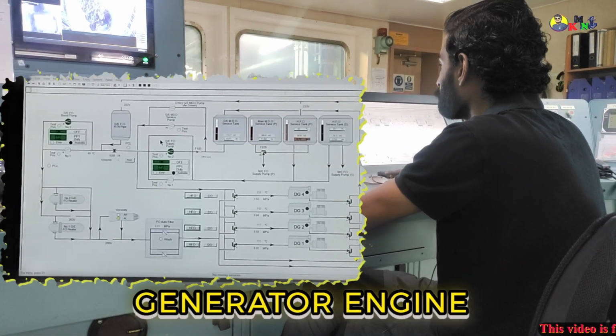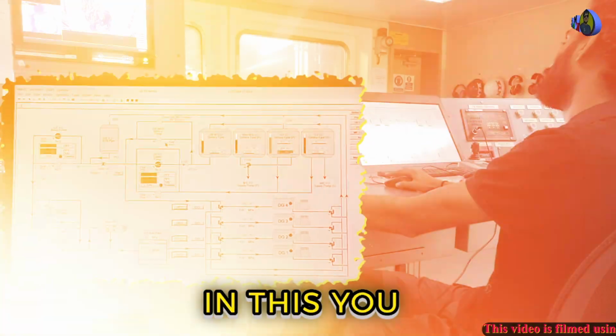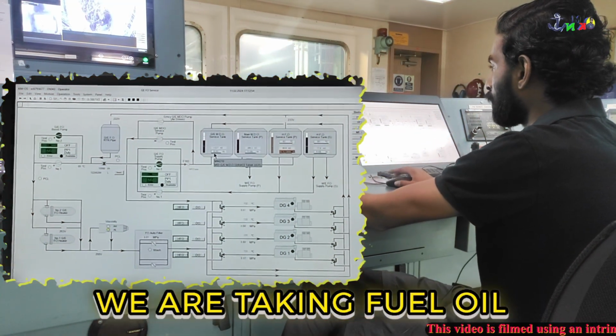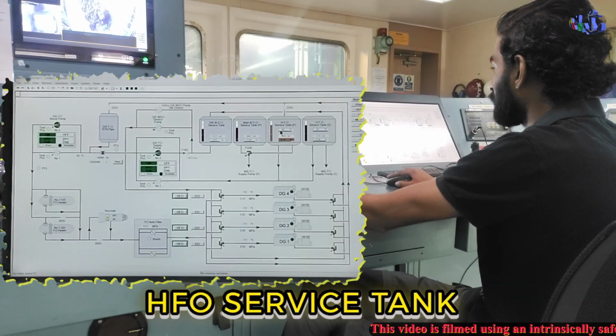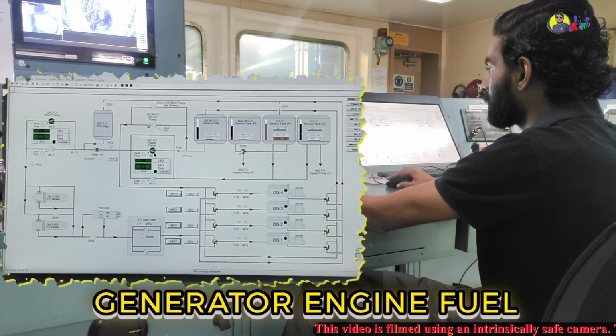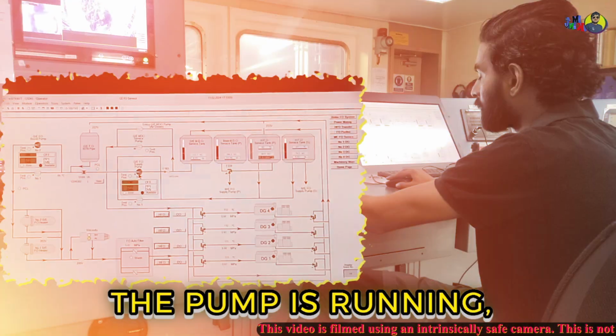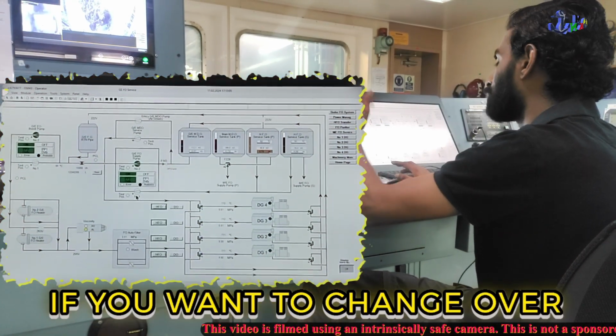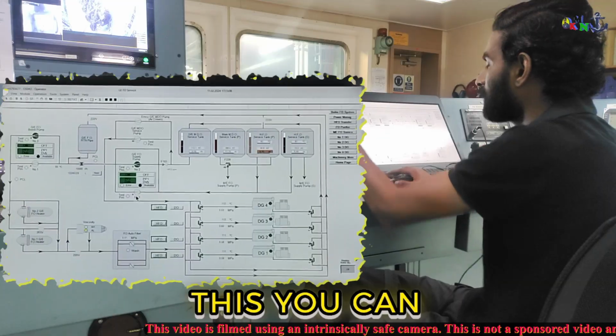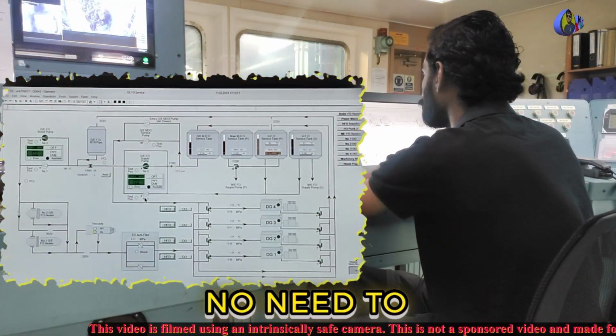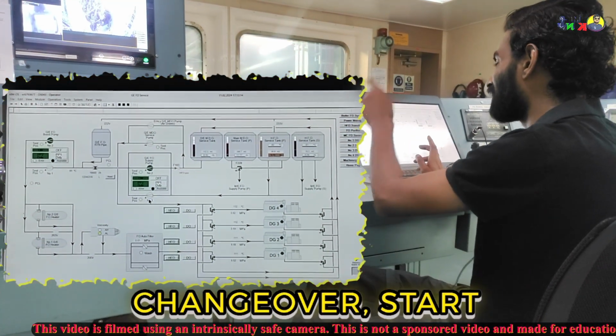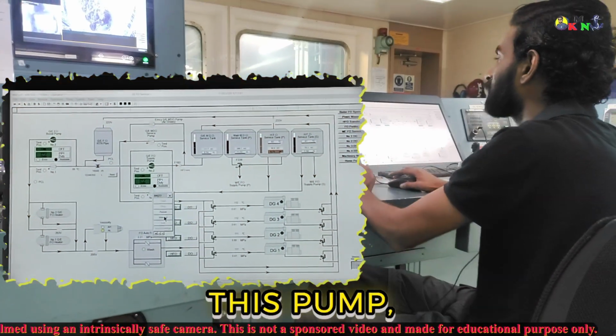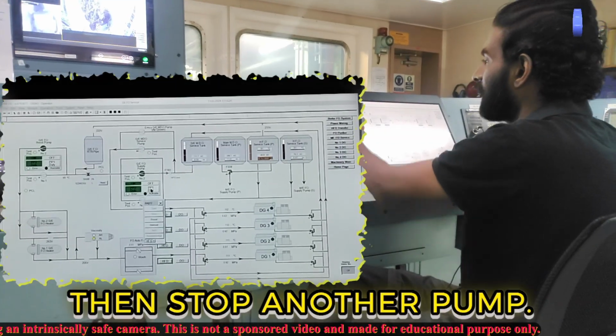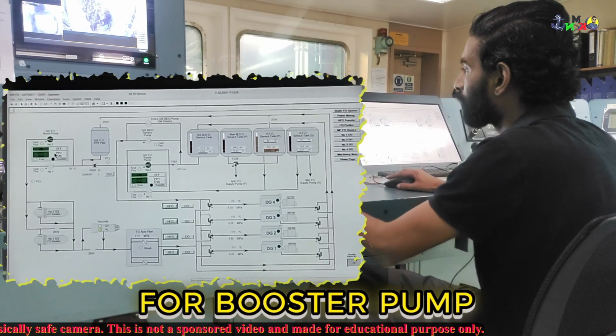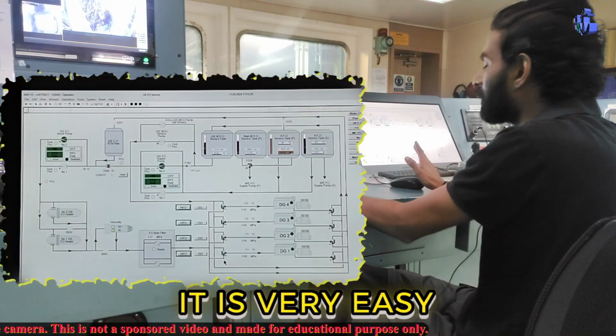We'll move to the generator engine FO service diagram. Here you can see we are taking fuel oil from the HFO service tank, and from here the generator engine fuel oil supply pump is taking suction. One pump runs, the other is standby. If you want to change over the pump from 1 to 2 or 2 to 1, you can do this directly from here, no need to go to the local side to change over and start another pump. Everything can be done from here. Just put it to manual, start the pump, put it to duty, then stop the other pump. Same for the booster pump. It is very easy to understand.